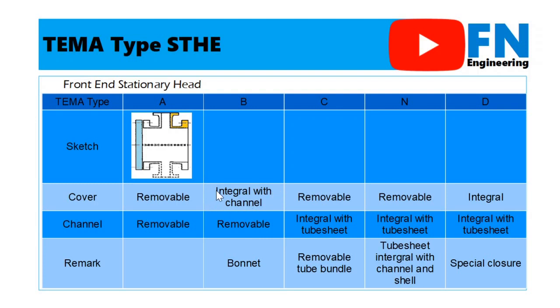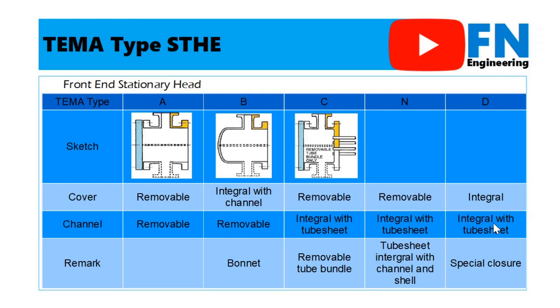using a bolting connection. Next, type B, or commonly called bonnet type. This type uses a removable channel, but the cover is integrated with the channel. This type is the common head type of shell and tube heat exchanger in my experience. The next is type C and type N. These types are similar. They use a bolting connection in the cover and the channel is integrated with the tubesheet.